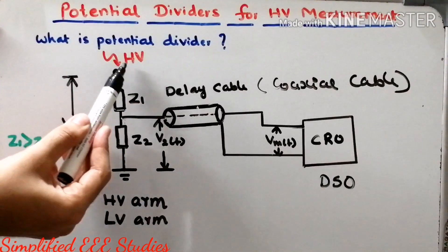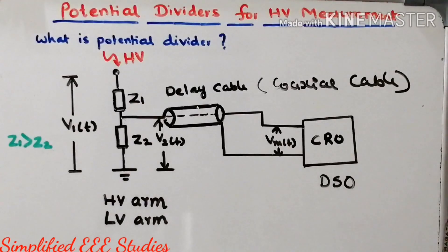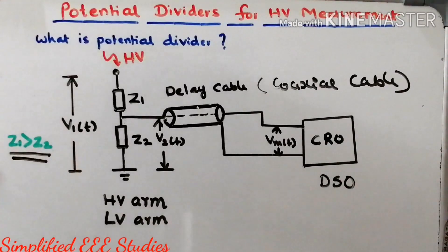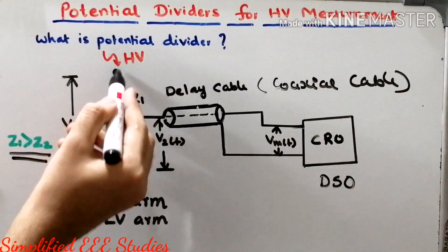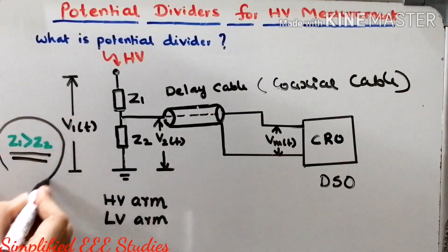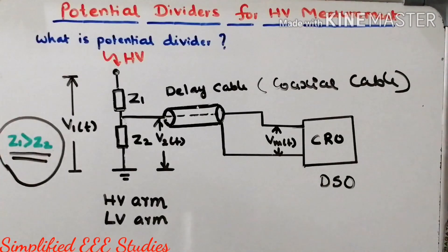Our main intention is to measure the voltage which has been applied externally — that is the ultimate goal. Through the potential divider, this can be easily measured. One important design consideration is that the impedance Z1 will always be greater than Z2, because Z1 corresponds to the high voltage arm and Z2 corresponds to the low voltage arm. While designing, you must ensure that Z1 is always greater than Z2.